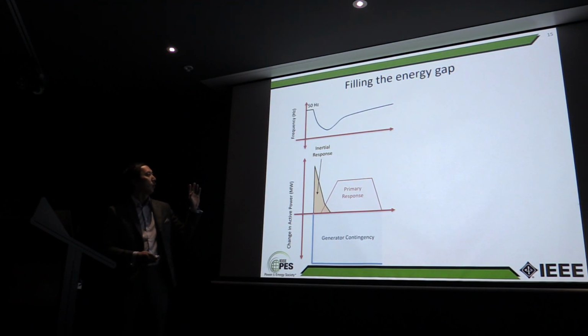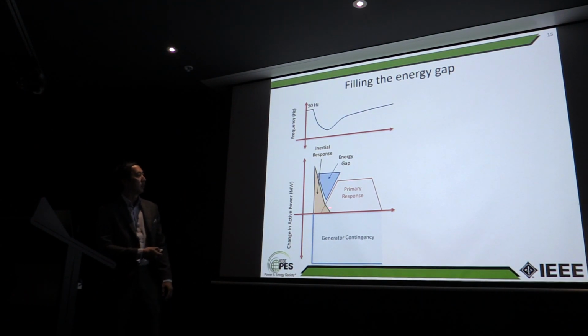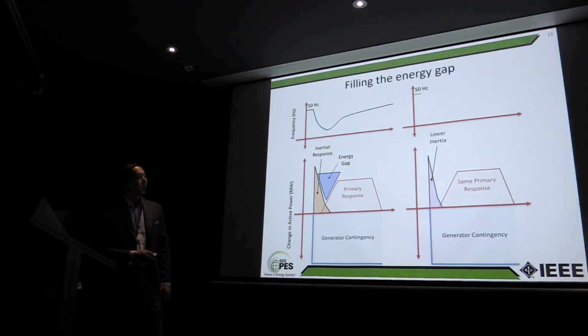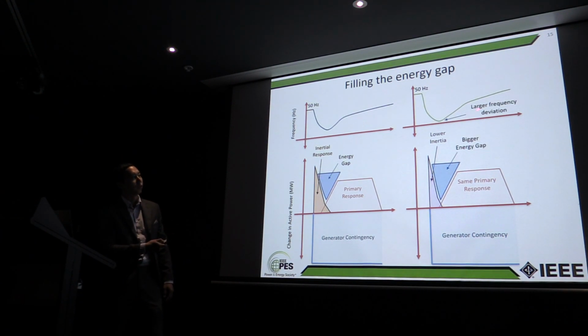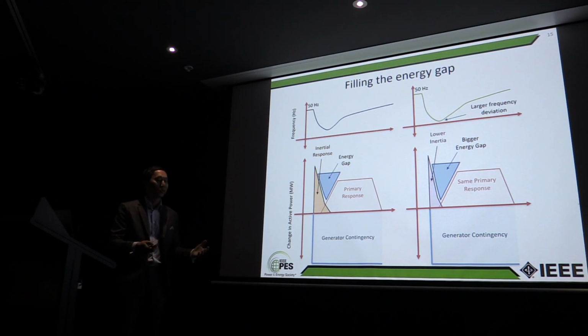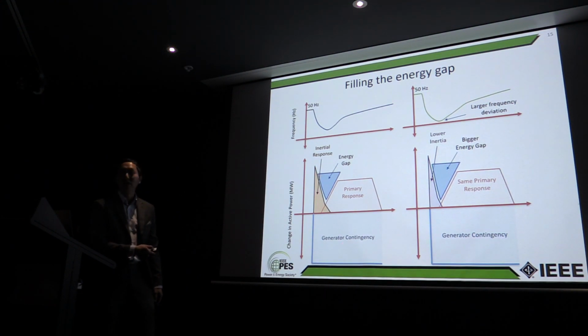And what happens is that there's actually an energy gap here. So the reason why the frequency falls is because if you actually recovered all of that generator contingency, if you recovered all the energy very quickly, frequency would just be stable, just be 50 hertz. You have inertia and you have the primary response, but you actually have a gap here of energy. And that gap basically determines how much you fall and how much the nadir is. And so what happens when you have lower inertia but the same primary response is you're going to have a bigger gap. And that causes this larger frequency deviation here. And that's really the basis of all this stuff. It's really just about energy and energy replacement after a generator contingency.